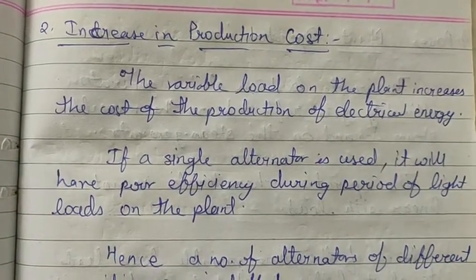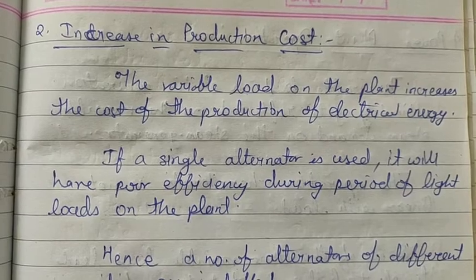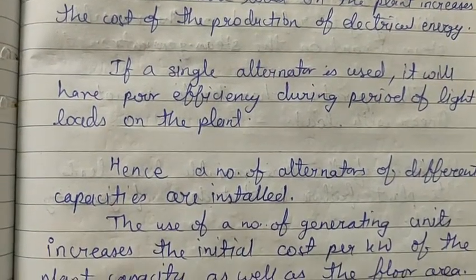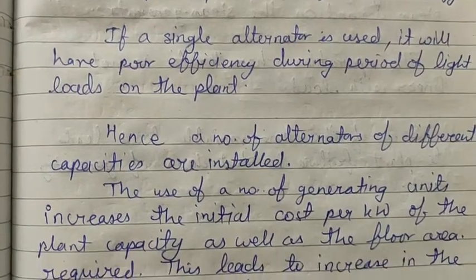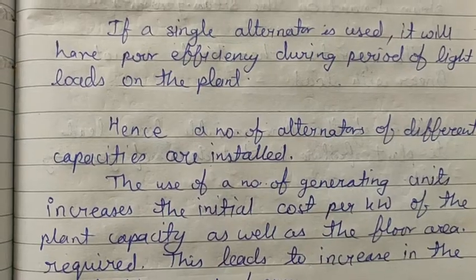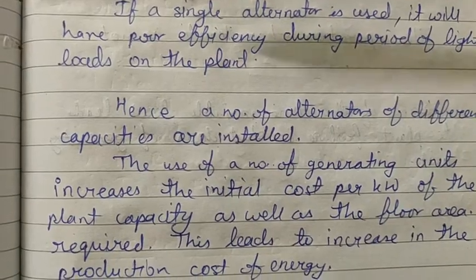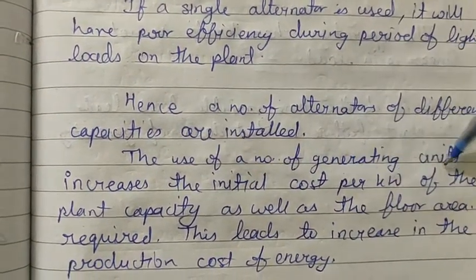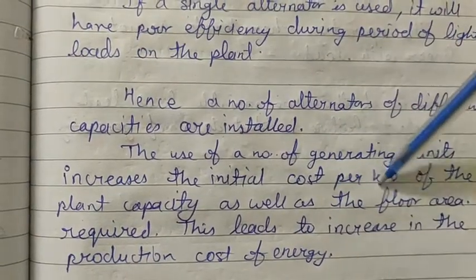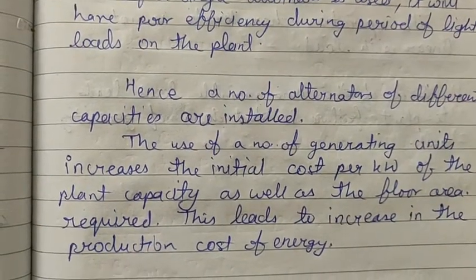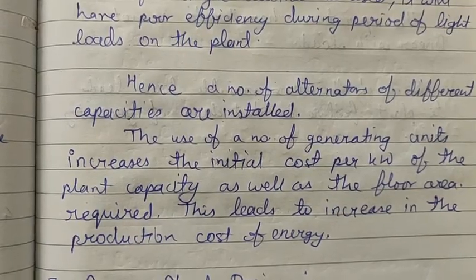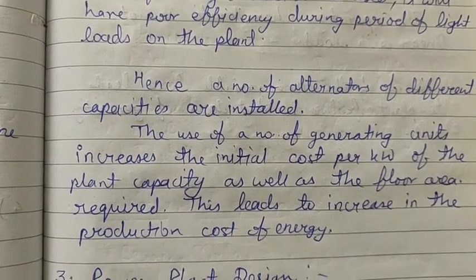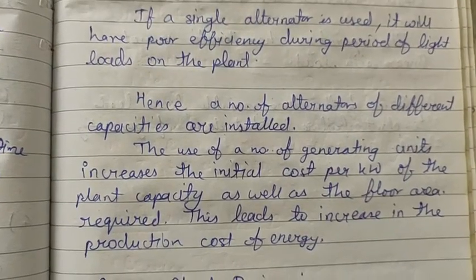During a period of light load, there will be waste. We can use a small alternator for small demand and a full-size alternator for full load. The use of a number of generating units increases the initial cost per kilowatt of the plant capacity, as well as the floor space required. If there is load variation, the installation cost will increase, which is why the plant's production cost will increase.